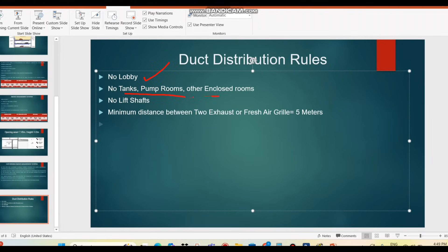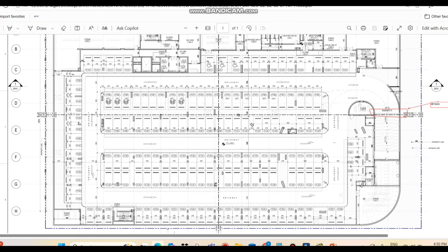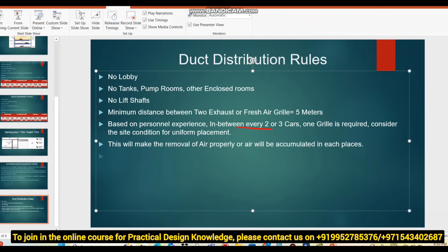Key points to note: lobby areas are excluded; tanks, pump rooms, and other enclosed rooms are excluded from the area calculation; lifts are not considered. Also, consider a minimum distance of 5 meters between two exhaust or fresh air grills. This is based on practical experience. The exhaust grills (return grills) should be placed near the car parking areas where CO levels are highest, at different locations to ensure proper ventilation across the entire space.